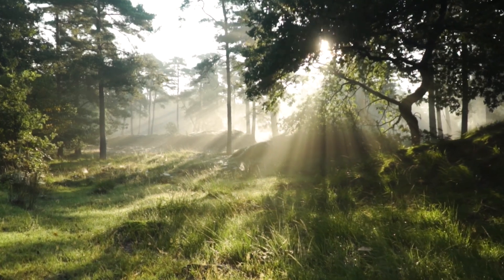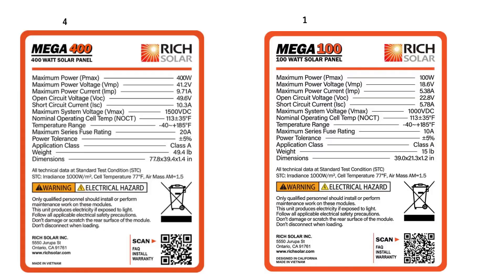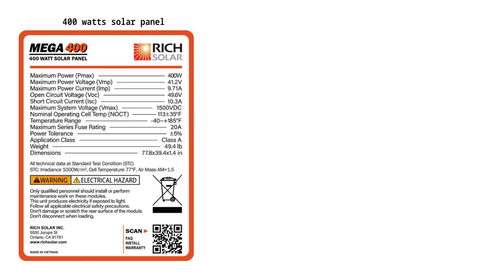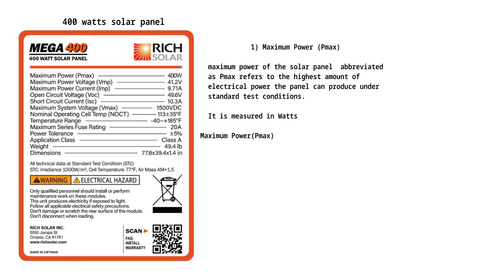Now that we have understood the standard test condition, let us look into each of the technical specifications of a solar panel and the role they play in the solar panel's power generation. 1. Maximum power. Maximum power, abbreviated as Pmax, refers to the highest amount of electrical power the panel can produce under standard test conditions. It is derived from the maximum power voltage (VMP) and maximum power current (IMP). Multiplying VMP by IMP gives you the maximum power of the solar panel in watts.